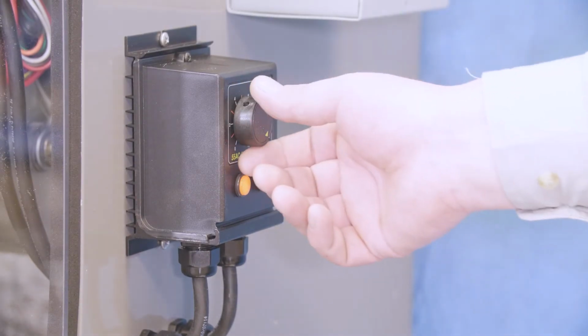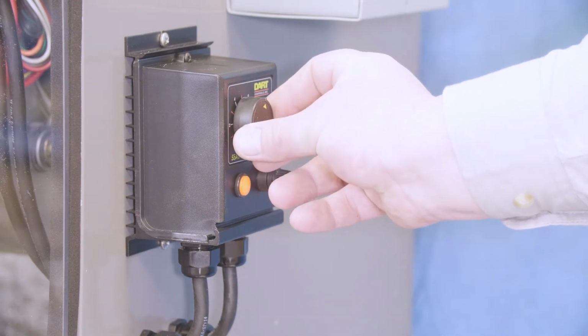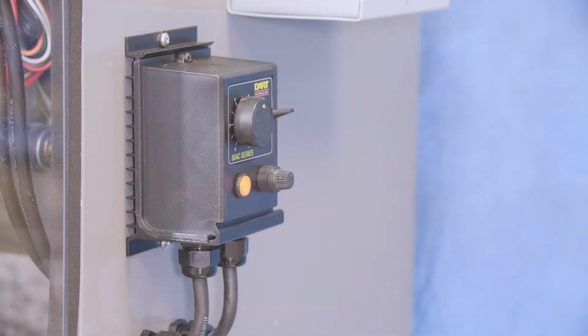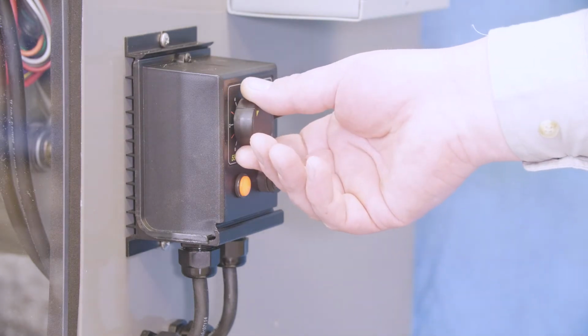Now, what happens if we kill the indoor fan? We've got a rheostat on the side of this unit, and we can slow the indoor fan to represent a filter getting dirtier and dirtier, or we can just turn it all the way off and represent a failed fan completely. You will see that the heat transfer changes there as well. The coil starts getting colder because it's no longer absorbing heat, because we're not moving air across it. So the second lesson is showing how heat transfer works and using the fans to show how it will affect the refrigerant capacity, the refrigerant pressures, and the temperature drop as well.